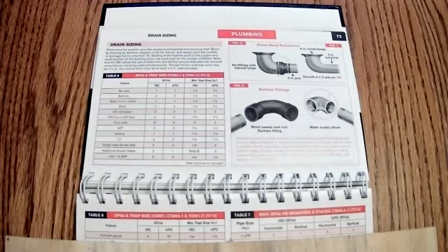Note that the IRC allows for the bathroom and the kitchen groups to be taken into account, and some fixtures not being used simultaneously. Though the kitchen sink trap arms may be 1.5 inches, the vertical drain must be at least 2-inch pipe diameter.